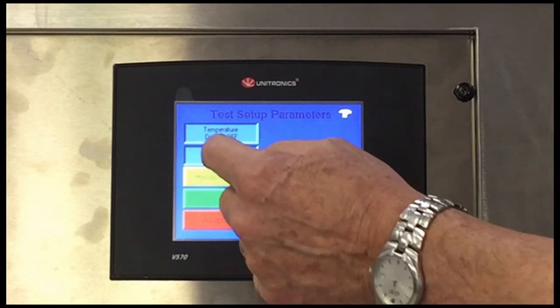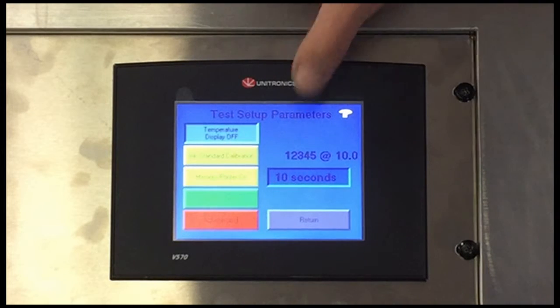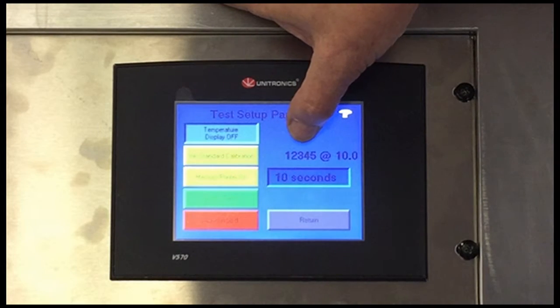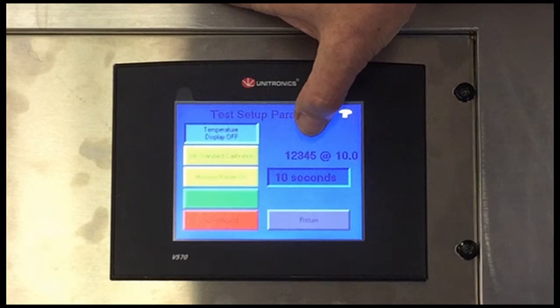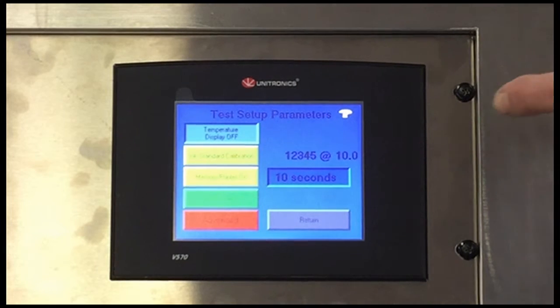If we choose an ink calibration, we turn that on. Now you'll see there's a number here which just happens to be keyed in 1, 2, 3, 4, 5. What that is, when you actually do the calibration with the ink, it allows you to key in a product number or a lot number as a reference for the ink standard that it was calibrated to.